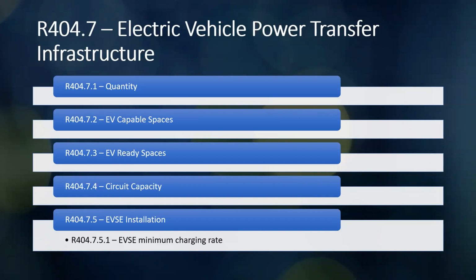And then the EVSE installation, it also points at UL 2202 and UL 2594 for different occupancies for that as well. The minimum rating for charging, it's showing on here, must be able to be capable of charging of not less than 6.2 kVA or 30 amp breaker at 208 and 240. Then it says we're serving EVSE spaces allowed to have circuit capacity of not less than 2.7 in accordance, and it says it shall be controlled by an energy management system, also capable of simultaneously charging of not less than 2.1 kVA. So if it's going to be sharing and it's one control system, it needs to at least do a 2.1 kVA per space to actually have that fast charging, or at least not a really slow charging for each one of those capacity.